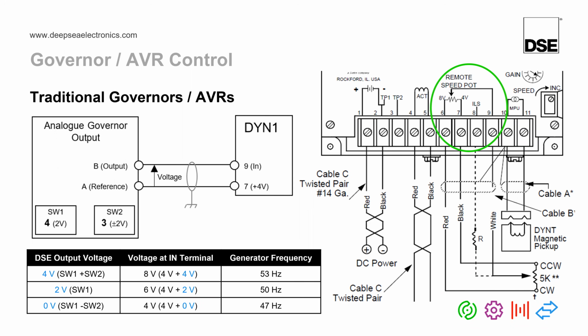This is because the way the DSE module works is it actually generates a voltage across its output. And the voltage we generate depends on what speed we want that generator to run at. So in this case, if we were to look at the voltage at the terminals of this governor here, it's still the same as it was in the previous slide. 6 volts to run at 50 hertz, 4 volts to run at 47 hertz, 8 volts to run at 53 hertz. That's still exactly the same.